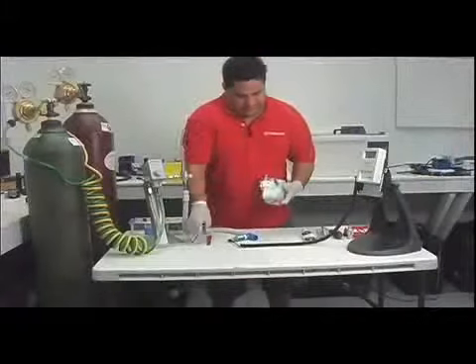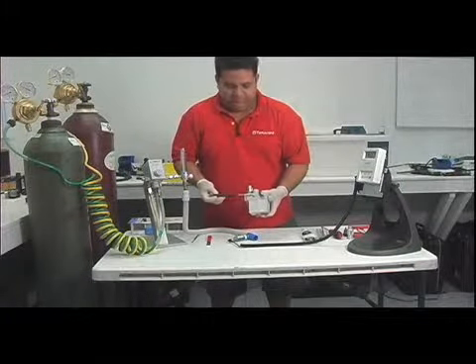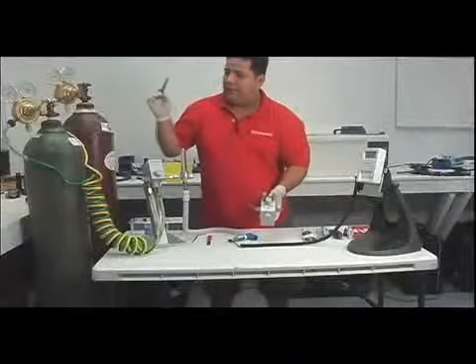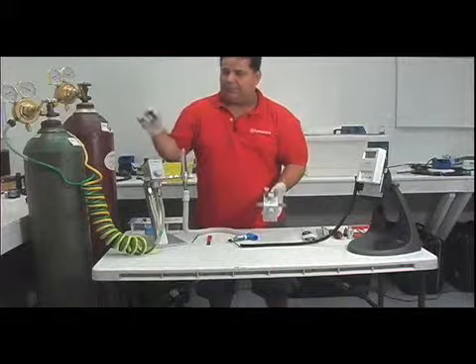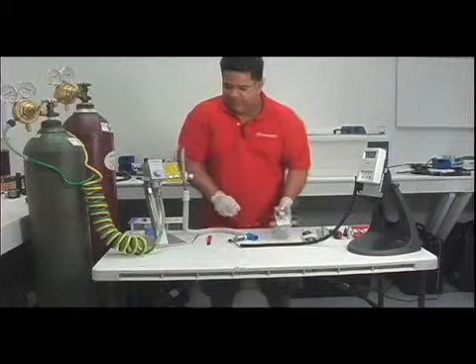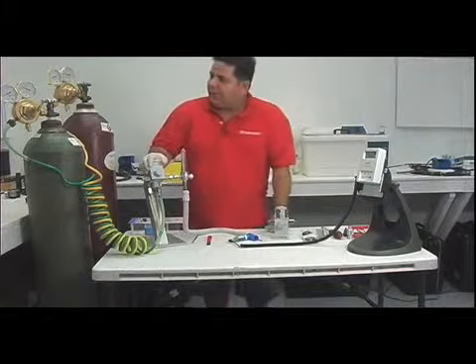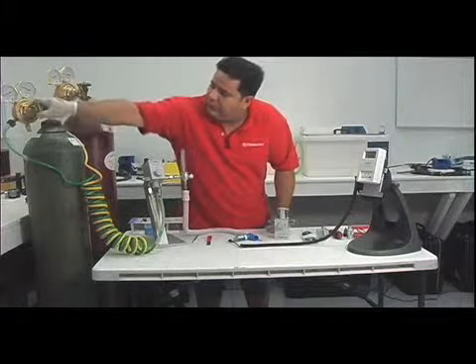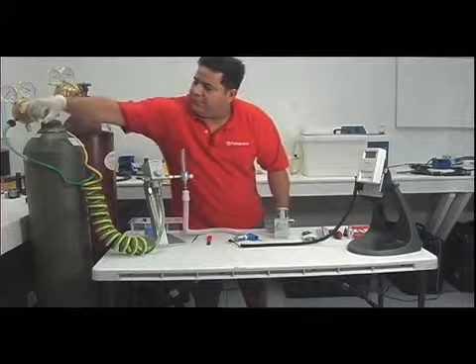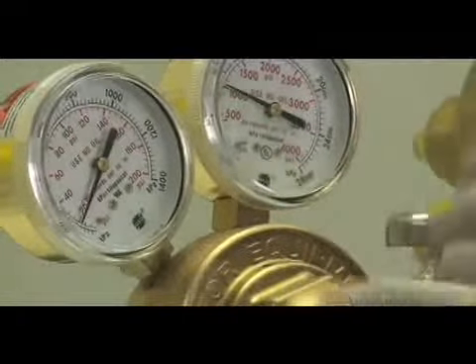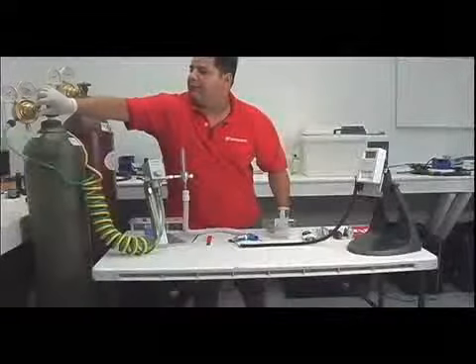You can notice that we have these calibration screws for the alarm. So we have one on the oxygen side, and we have one on the medical air side. So by calibrating these two screws, moving it in and out, we are going to have the proper calibration whenever we have a difference of 20 psi to make the alarm go off. And we're showing that over here. This one is fully calibrated, so we're just going to show that. If we reduce our pressure down to 30 psi and lower, the alarm starts going off. So that's what we need to have.